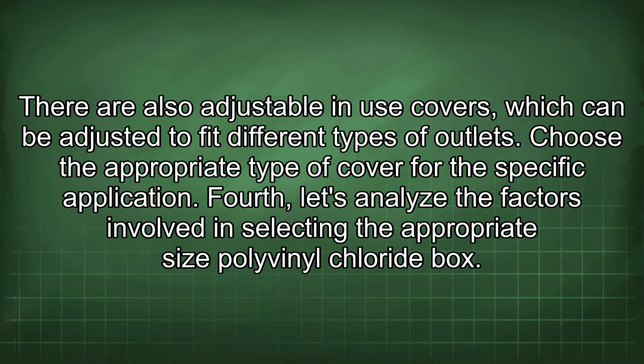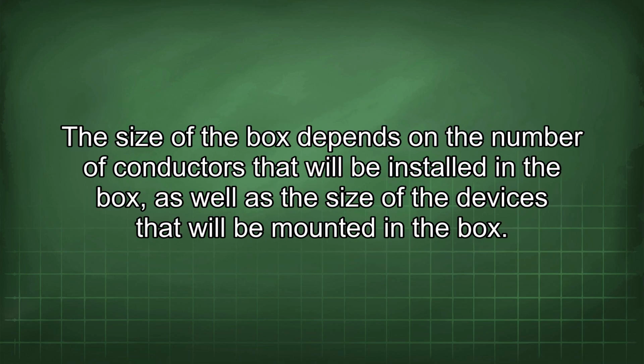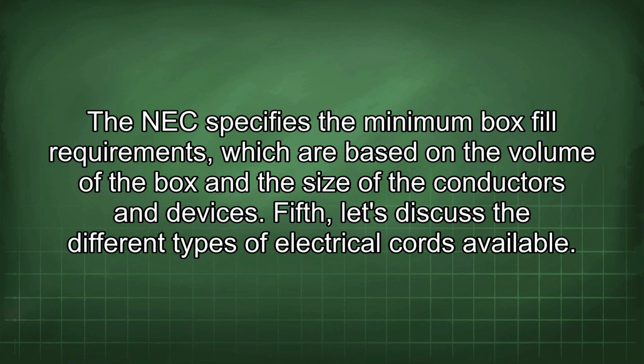Fourth, let's analyze the factors involved in selecting the appropriate size polyvinyl chloride box. The size of the box depends on the number of conductors that will be installed in the box, as well as the size of the devices that will be mounted in the box. The NEC specifies the minimum box fill requirements, which are based on the volume of the box and the size of the conductors and devices.